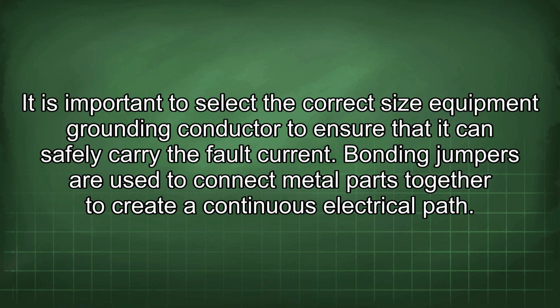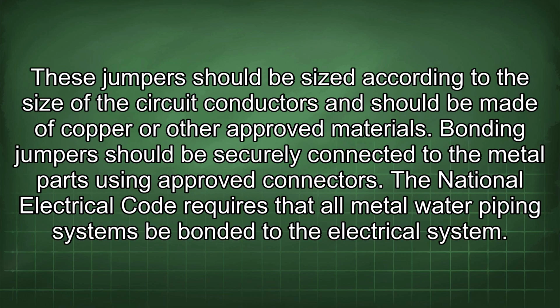current. Bonding jumpers are used to connect metal parts together to create a continuous electrical path. These jumpers should be sized according to the size of the circuit conductors and should be made of copper or other approved materials. Bonding jumpers should be securely connected to the metal parts using approved connectors.